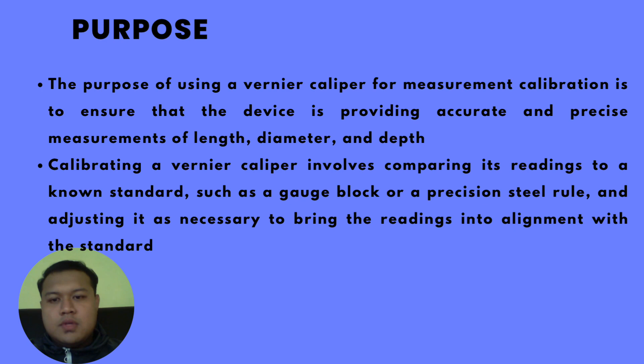Next, the purpose. The purpose of using a Vernier caliper for measurement calibration is to ensure that the device provides accurate measurements of length, diameter, or depth. Calibrating a Vernier caliper involves comparing its reading to a known standard, such as a gauge block or a precision steel rule, and adjusting if necessary to bring the reading into agreement with the standard. We chose the Vernier caliper because it is a part of the equipment that we use in industry and is very important equipment to calibrate all the material in industry.